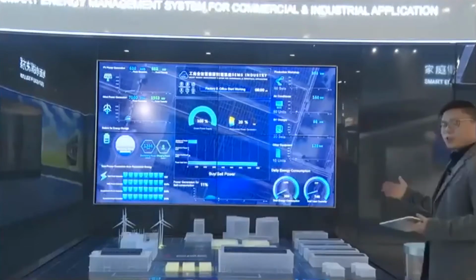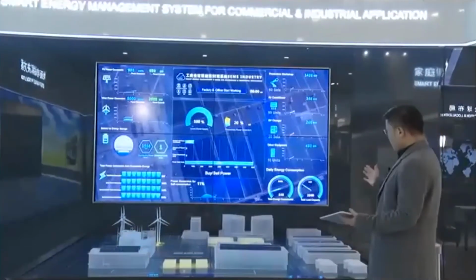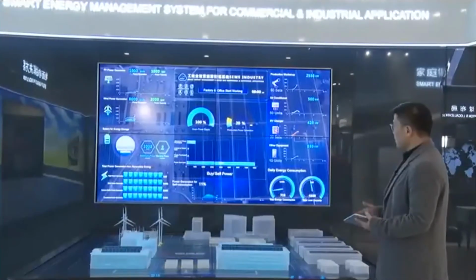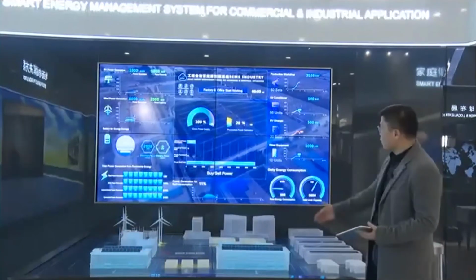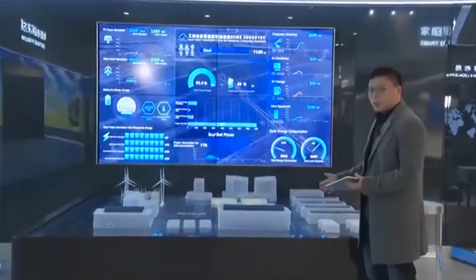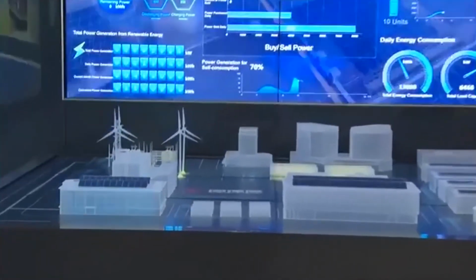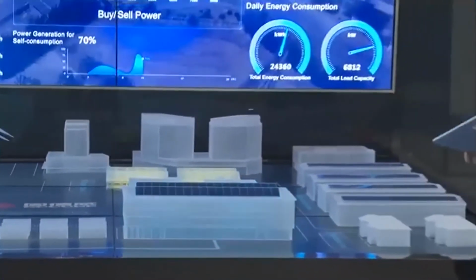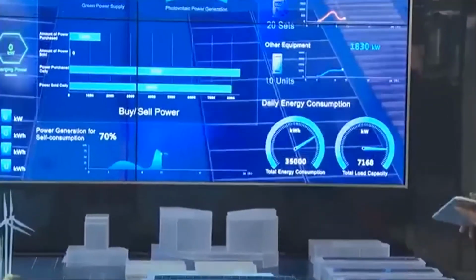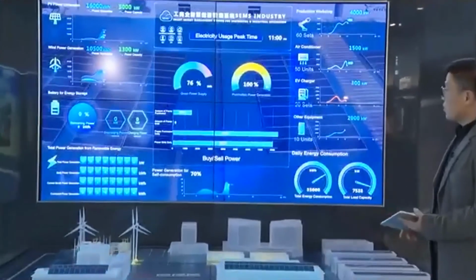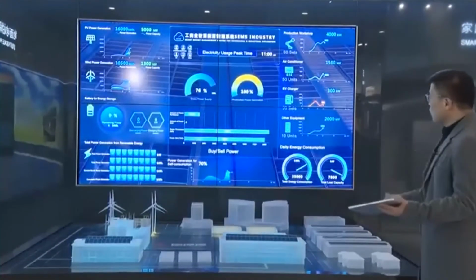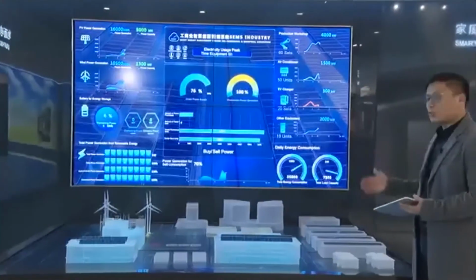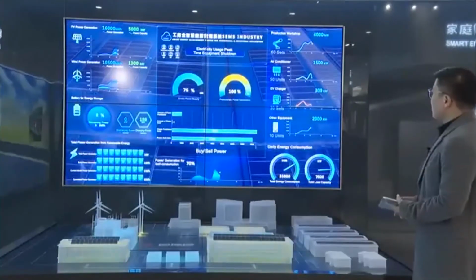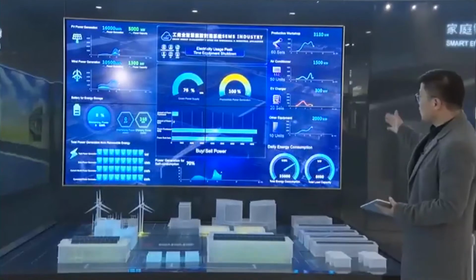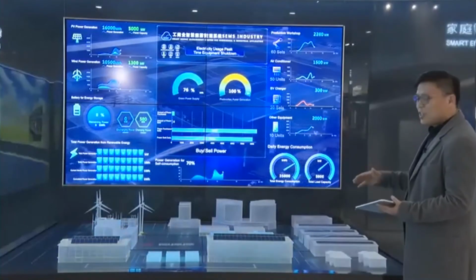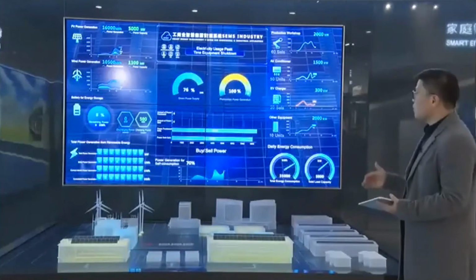Okay, this is our energy management system for industry. Let's say 8 a.m. in the morning, the beginning of the day, the energy consumption is not that much, so everything can be supplied from the storage systems. Now it comes to 11 a.m., so the power consumption is really big. The storage system will continue to supply, and the PV system will be 100% supplied to all the loads. And because the consumption is big, maybe you need to take some power from the grid. All the load consumption will be displayed here.